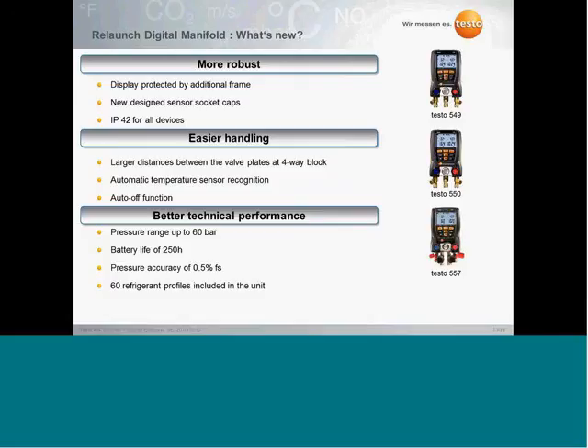Those of you who already use digital manifolds of Testo will know that if you plug in a temperature probe, you need to turn the instrument off and on again to start working. This is something which is very annoying in everyday work. So with the new instruments, these are automatically recognized even if they are plugged in during operation. With another function, if your instrument is in your car or in your toolbox, for example, and you leave it turned on, it will shut down after a while automatically, which will save battery and will prevent you from going to your car some days later and finding a dead instrument.